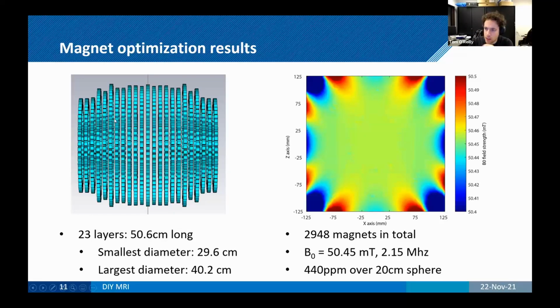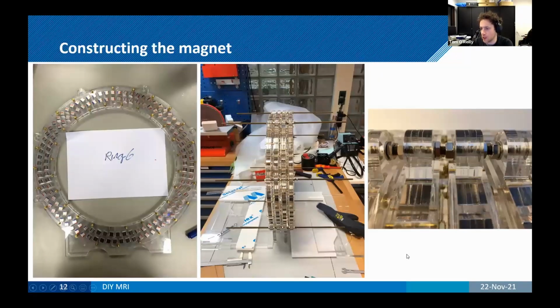You really see that effect where you have your smaller ring diameters towards the edges and your bigger ring diameters in the middle to prevent that field from dropping off. And this used about 3,000 magnets in total. And it's supposed to have a homogeneity of 440 parts per million over 20 centimeters, which is really pushing it for whole head imaging, but good enough-ish. Definitely, if you can get that 20 centimeter bigger, it's definitely better.